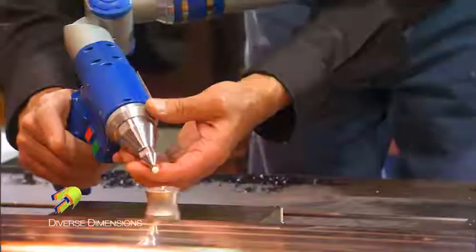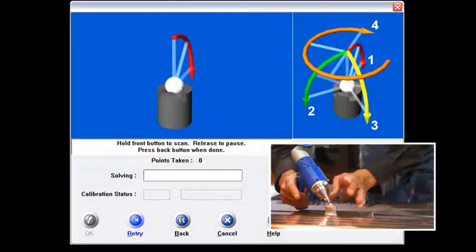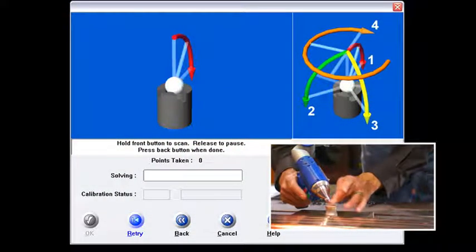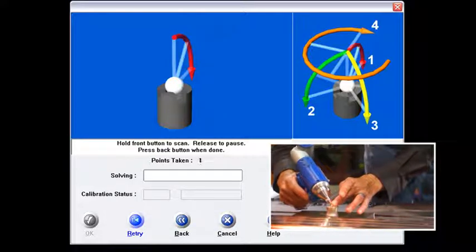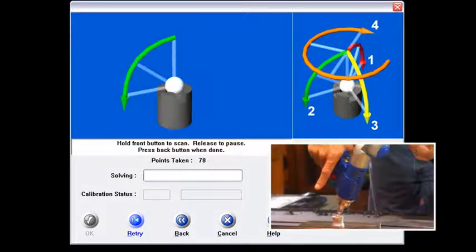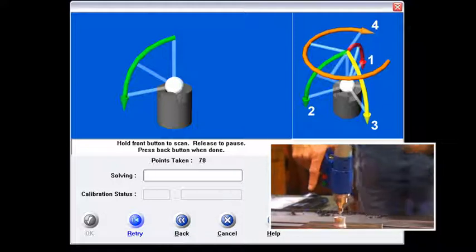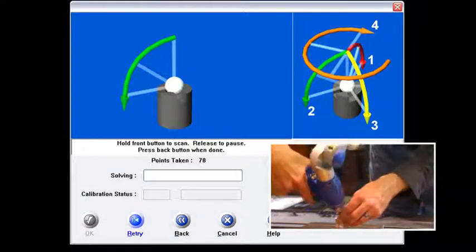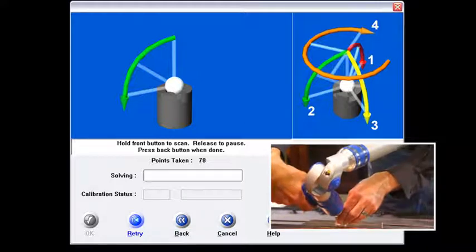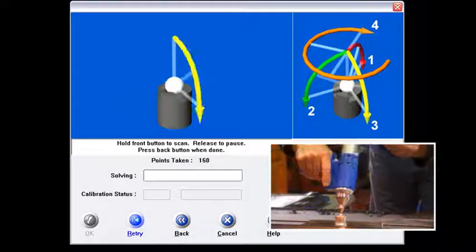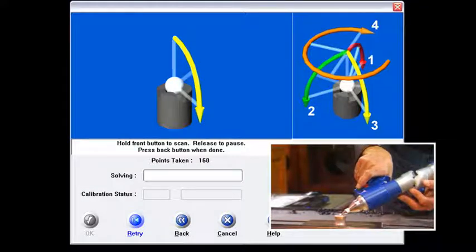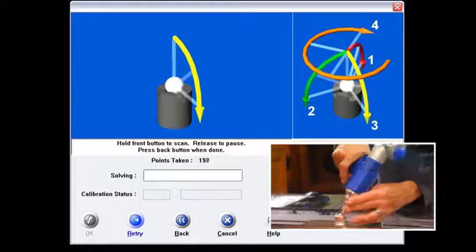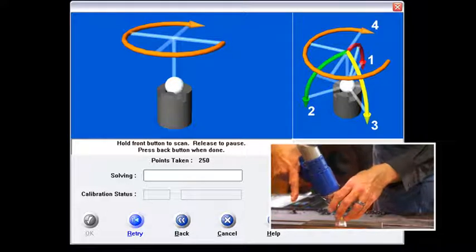What I do is I put the probe inside of that cone and then I usually start with my finger just lightly touching that probe so I know it won't come out of the cone. Then I'll push the green button and I'll swipe up and let go. I'm swiping a little bit more than a 90 degree path. Then I'll go into this other opening, I'll punch the green button, swipe it past 90 and let go. I'll go into this third opening, punch the green button, swipe up to there and then I'm going to let go.